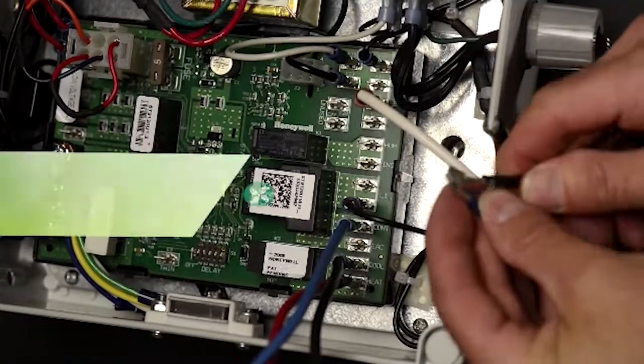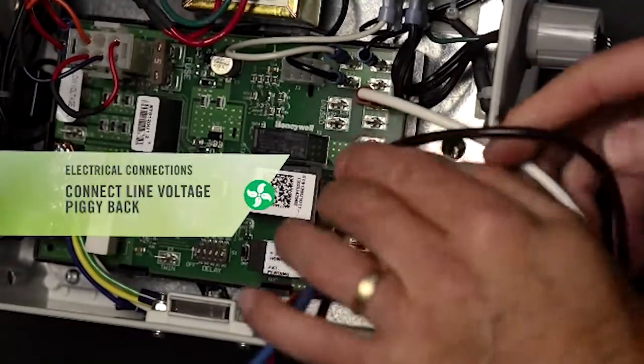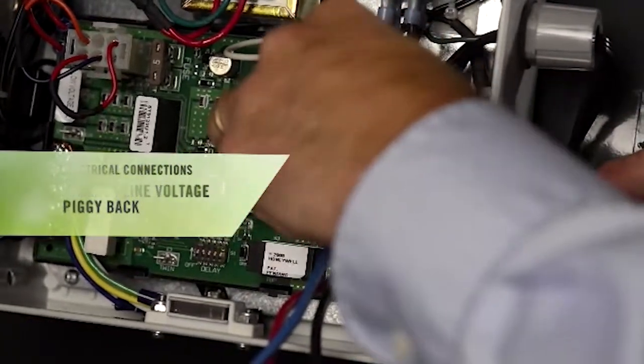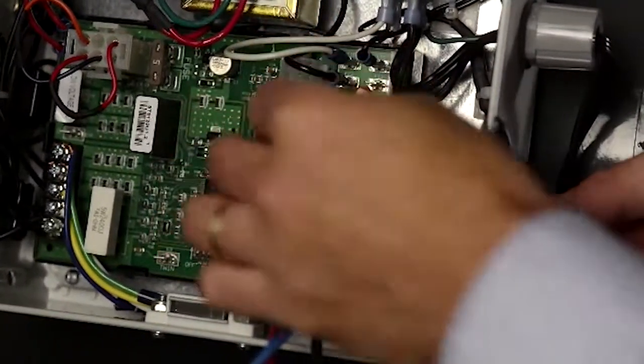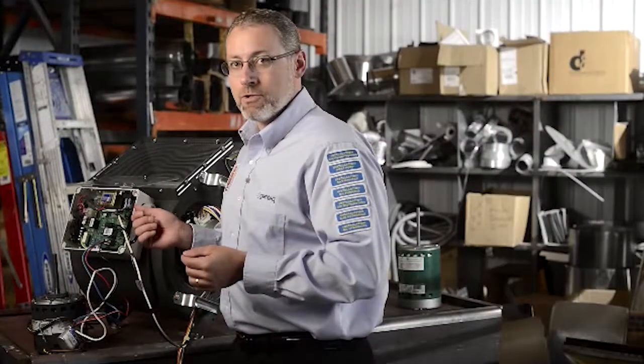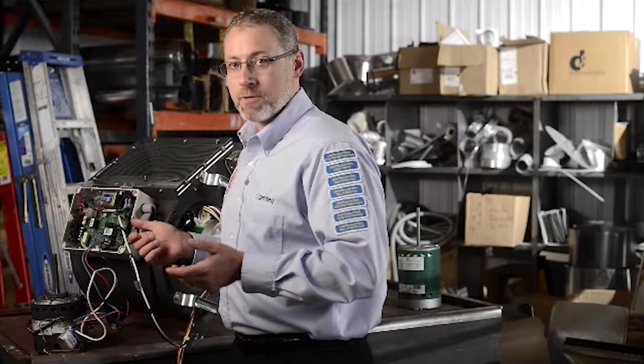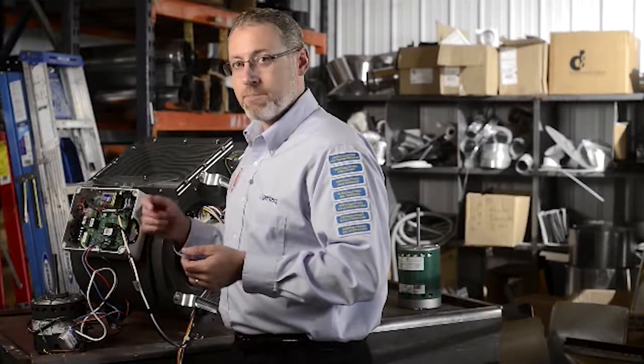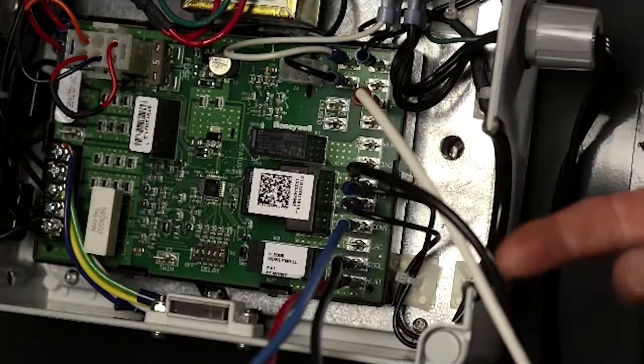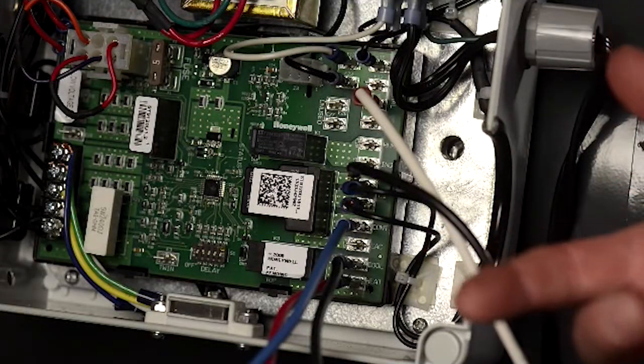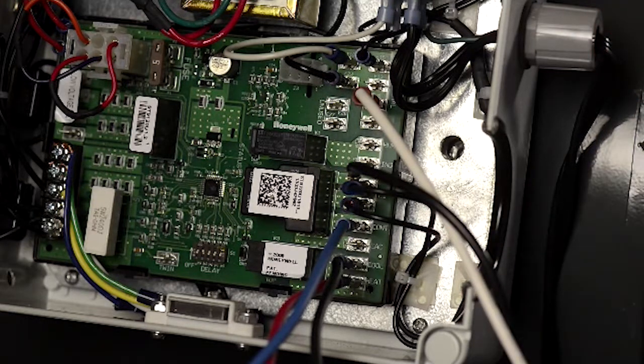We're going to put it on the back of the piggyback, and we're going to connect that right back where it was. Oop, right back where it was. There we go. So if you notice, those two wires had 1/4-inch spade terminals on them. The line 1 wire had the piggyback on.